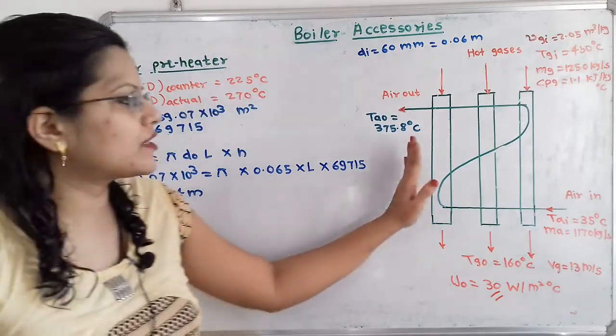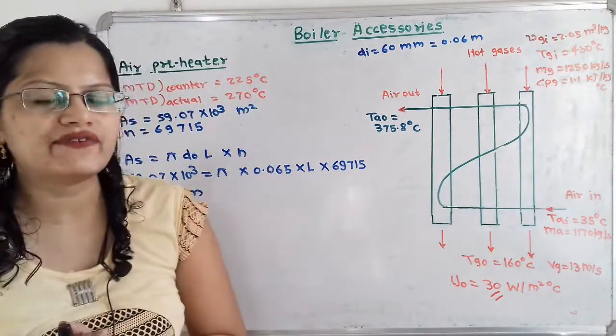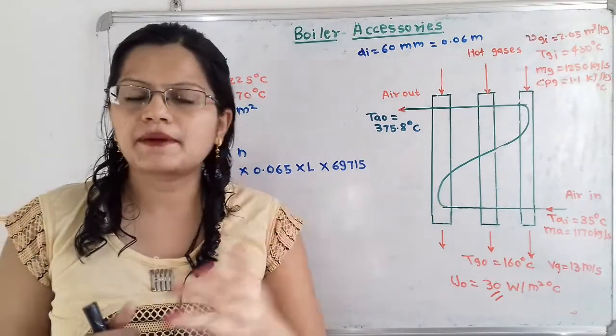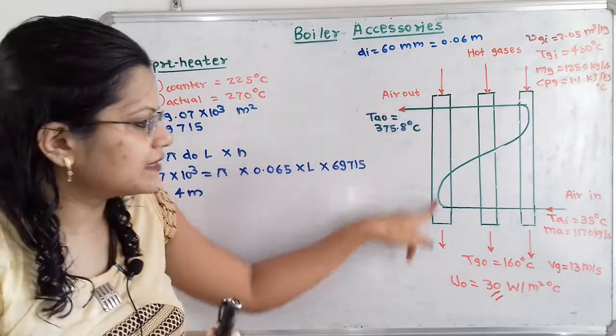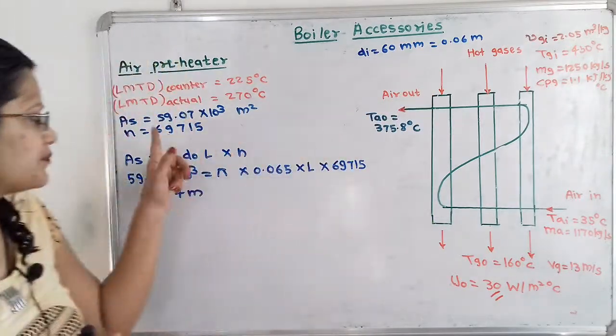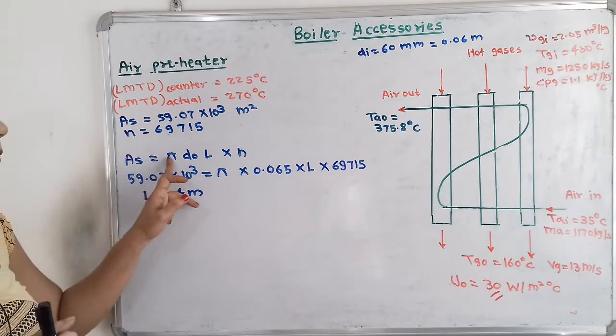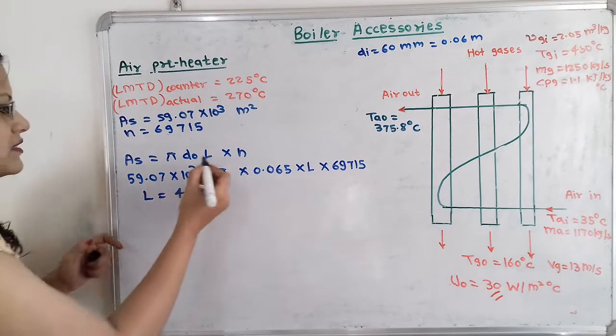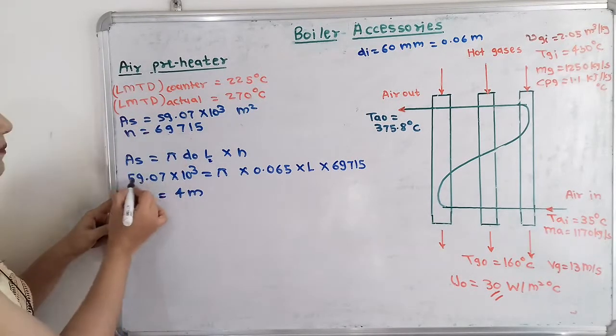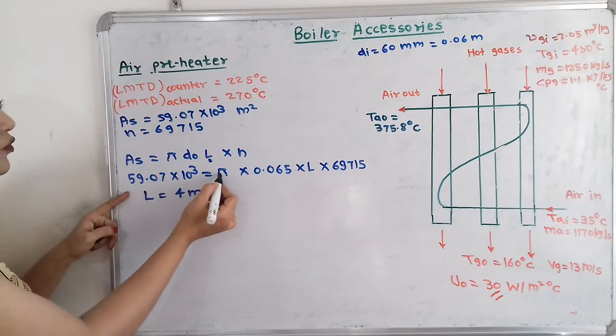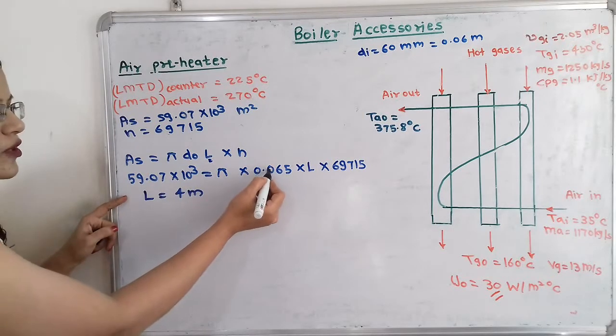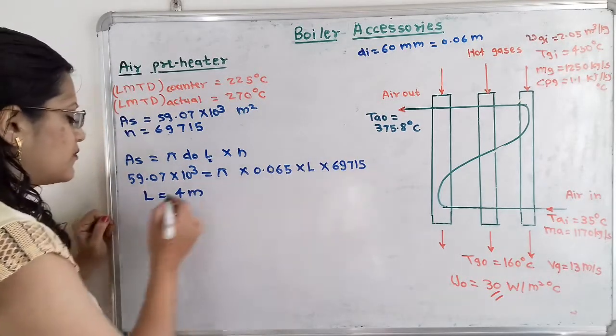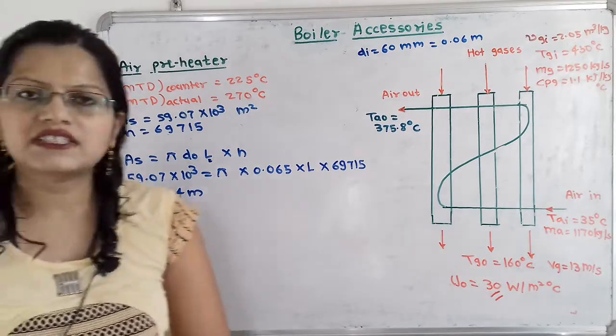Now we find the length L using the total surface area formula: AS equals pi times outside diameter DO times L times N. Substituting AS equals 59.07 times 10 raised to 3, DO equals 0.065 meter, and N equals 69,715, we solve for L. The calculated length of the tube is equal to 4 meter.